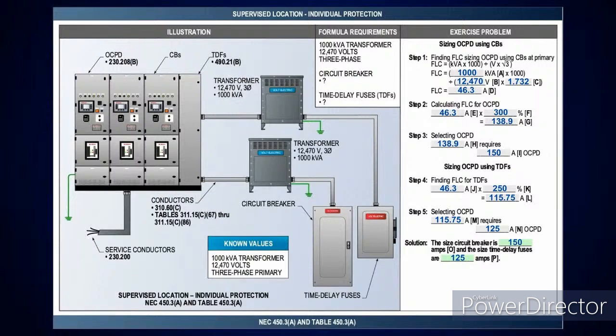The only time that doesn't apply was here at transformers. If you've got a note one in there, it says shall be permitted, so that means I can go up or down. But if it didn't have a note one, then we were dropping down if we were over 125%. And then the other one you'll see we'll get into is phase conversion, because you have to protect the conductor, and the conductor is taken at 250%. Those are two of the places in the NEC that I'm aware of that this rule of thumb doesn't hold true.